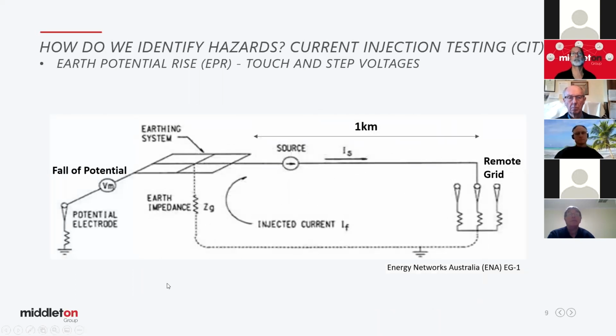So how do we identify these hazards that can be transferred around our sites? Well, we use current injection testing. In current injection testing, we can measure the earth potential rise, the rise at the site, the voltage of the soil at the site where the fault is. And we can also, through this technique on site, simulate a fault and measure a scaled down measurement of the touch and step voltages.